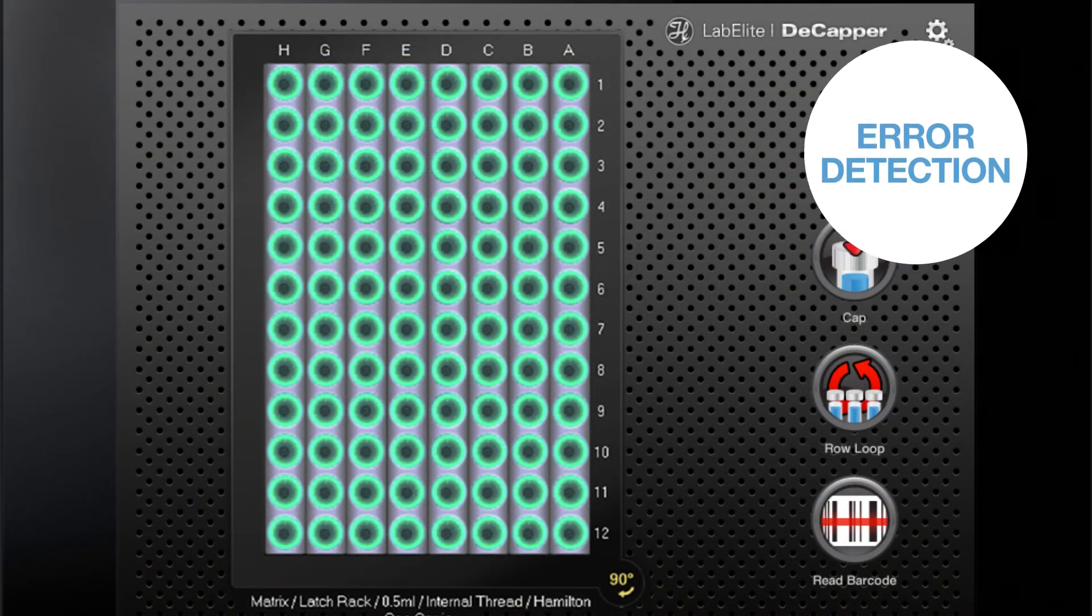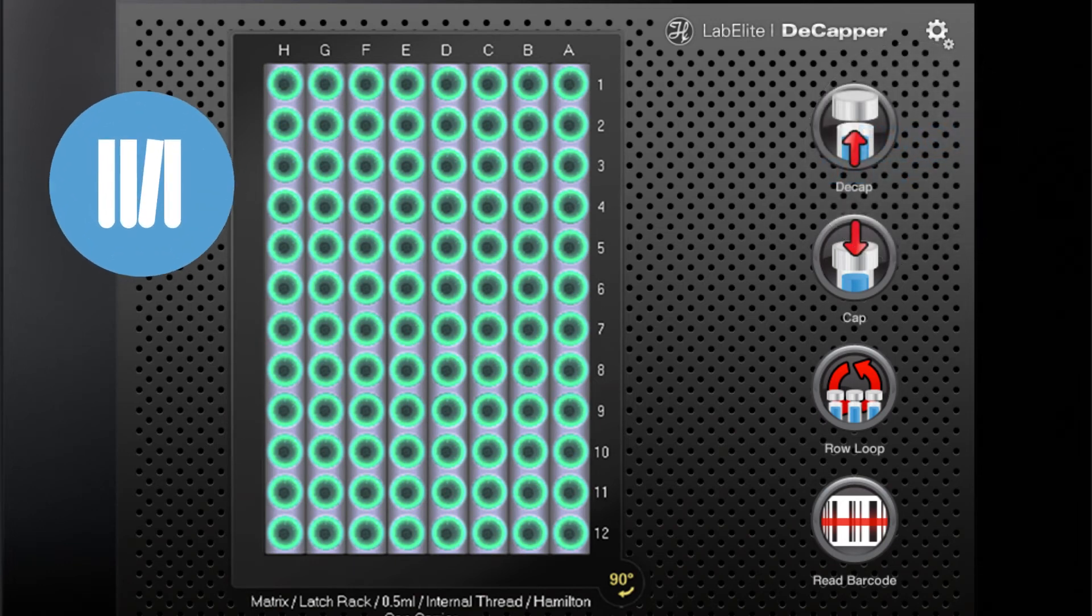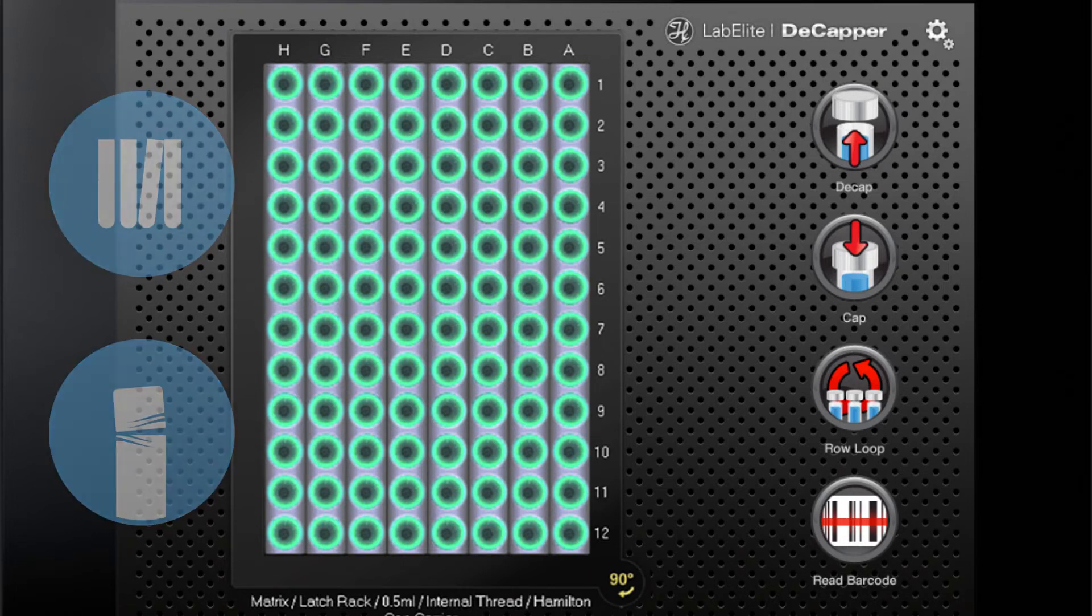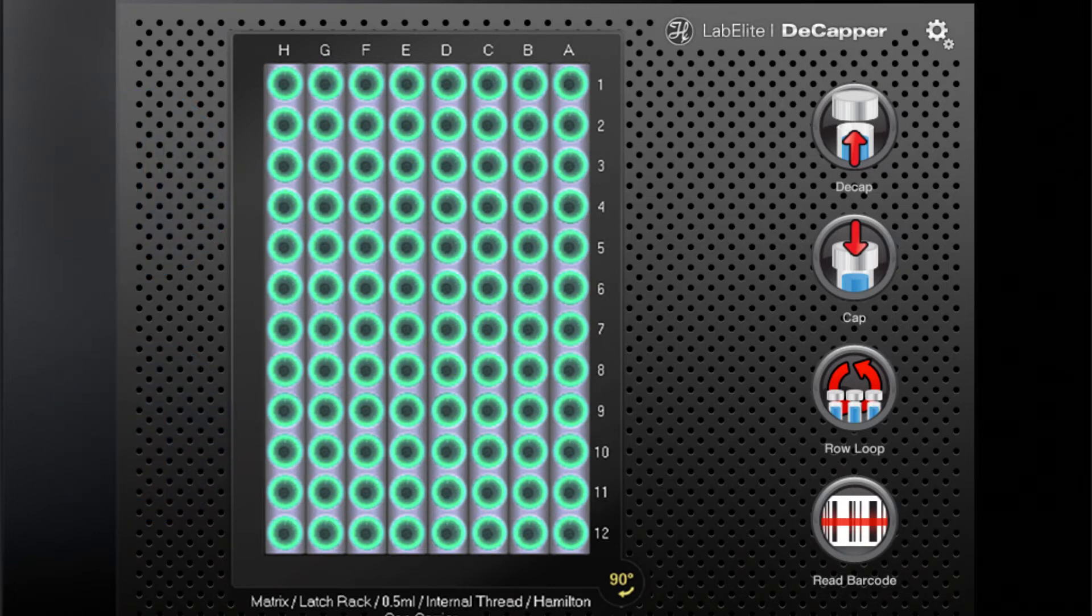Our Decapper features an automatic error detection function. Do you have a problematic tube? Or perhaps a cross-threaded cap? The device has feedback sensors in each channel that will alert you to any cap not torqued to the manufacturer's exact specifications.